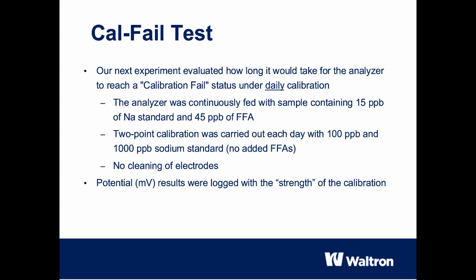fail under these conditions? For this experiment, we continuously supplied the analyzer with our sample of 15 ppb sodium and 45 ppb FFA. Once daily, we performed an automatic 2-point calibration using clean standards of 100 and 1000 ppb sodium, i.e. without FFA added. An important point here is that we did not clean the electrodes during the entire test to simulate the real-life effect of progressive contamination.